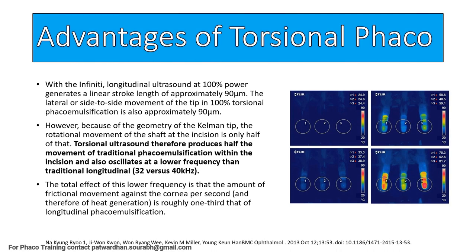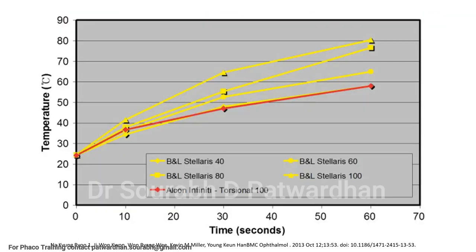Apart from that, torsional phaco also produces very less heat inside the anterior chamber as well as at the wound. Compared to longitudinal phaco, it is just one third of the heat produced, which is excellent. With torsional phaco energy, it is rare — I would say almost impossible — to have a corneal burn. This has been shown in various experiments measuring temperature increases around the phaco tip.